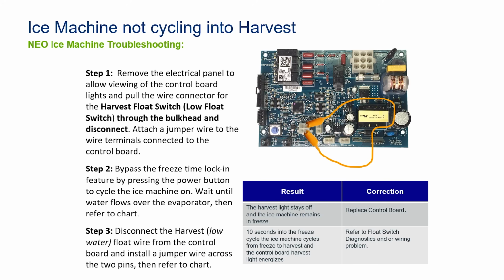Turn the ice machine on. About 10 seconds into freeze, you should be going into harvest. If you do, that proves that the float is the issue. You took an input device out of the circuit, you bypassed it, and you told the harness to tell the board that it's closed. That must mean that it's time to go into harvest.